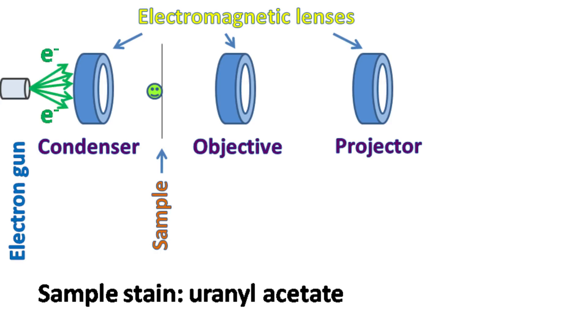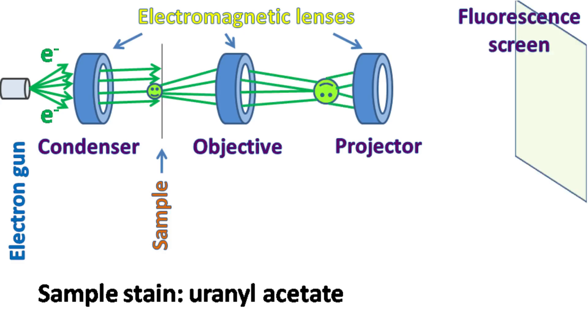Electrons are focused on the specimen using the condenser. The diffracted electrons by the specimen are collected by the objective lens. The electrons from the objective lens move through the projector lens, which projects the image of the specimen on the fluorescent screen. In transmission electron microscopy, the samples are usually stained with uranyl acetate.